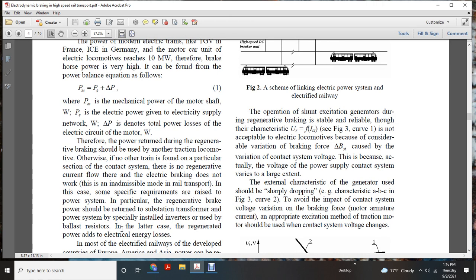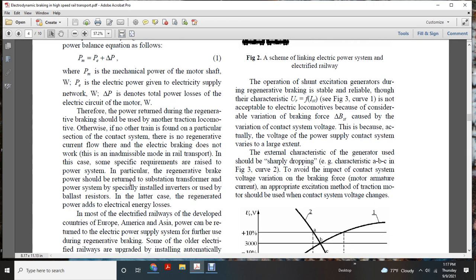Therefore, the power returned during regenerative braking should be used by another traction locomotive, unless there is no other train in that particular section of the contact system. There is no regeneration, the current does not flow, and electrical braking does not work. This is inadmissible in rail transport. In this case, some specific requirements related to the power system apply: in particular, the regenerative braking power should be returned to the substation transformer power system, and by specially installed inverters, or used by ballast resistors.